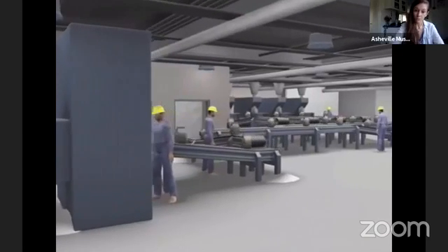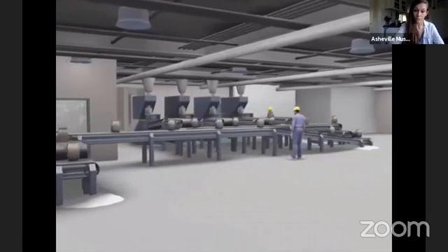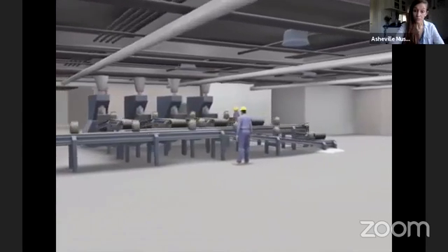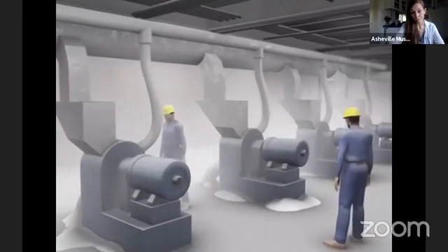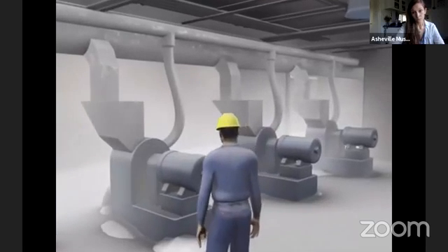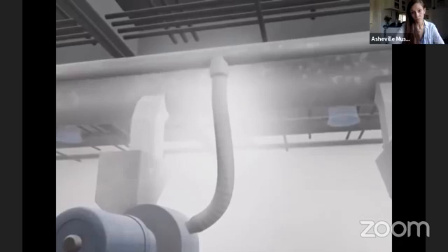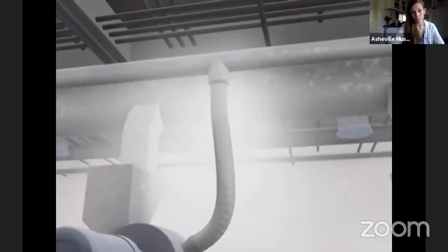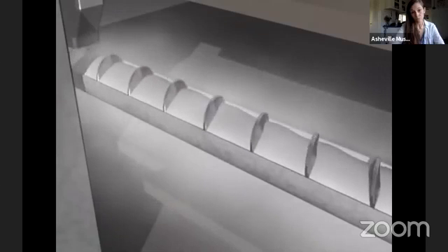During this process, sugar spilled onto floors throughout the work area. In places, the spilled sugar was many inches deep. This sugar also contained fine particles, which became airborne. In addition, hammer mills were used to crush the granulated sugar into powdered sugar, creating even more dust. The machines were connected to a dust collection system, but it was undersized and in disrepair, and it was not connected to the bucket elevators and conveyors.